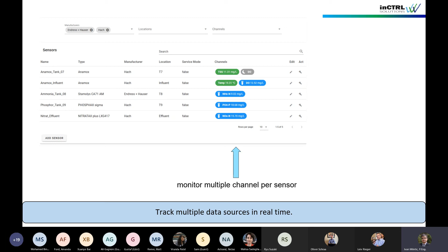If you look at this in the form of one sensor channel, in this case for temperature, for an ammonia effluent sensor, we could apply a control chart to see the difference between the laboratory and the sensor value as the laboratory and sensor values are coming in, so in real time or near real time.